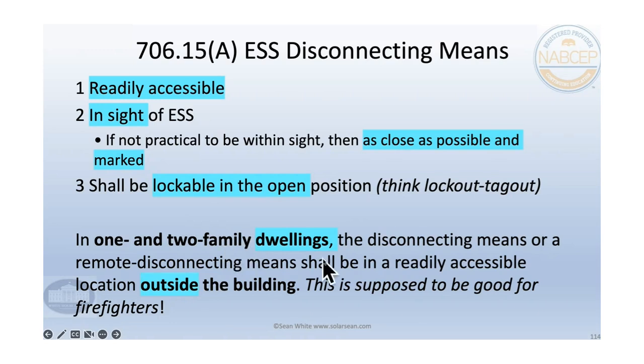For 1 and 2 family dwellings, you need to have the disconnecting means outside of the building, and we're going to look at how it can also be a remote type of thing. One of the things that people were having problems with is if you had the disconnecting means outside of the building and you were running all of your current through that disconnecting means, it could make an extra danger, because you have the conductors going from, say, your energy storage system to that disconnecting means still energized, but then you're shutting off all the loads coming out of it. So there's still some work to be done on this before we make it more like rapid shutdown or something like that.